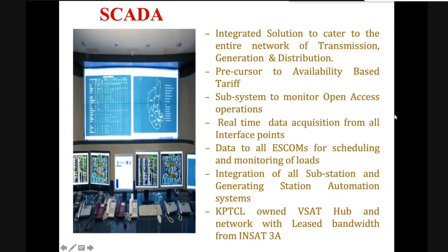So what will this SCADA give? Energy management, peak load, station and transformer load, current profile of different feeders, battery status, duration of interruption because of any faults, and we can operate the breaker, OLTC, and capacitor bank remotely.